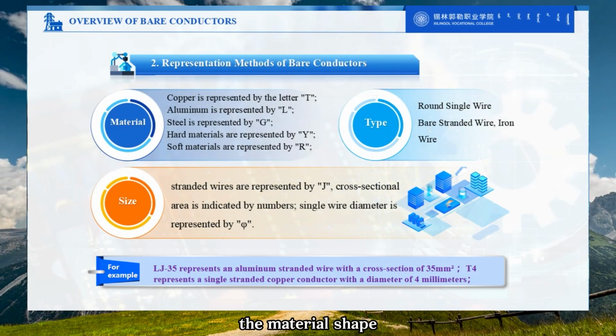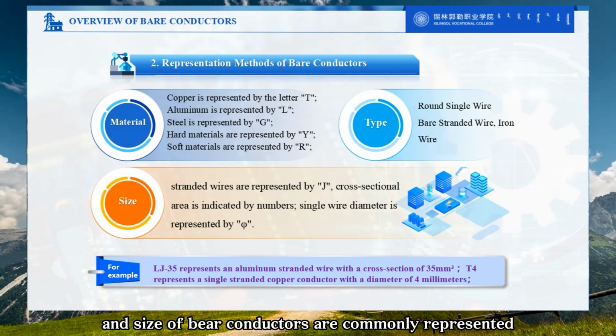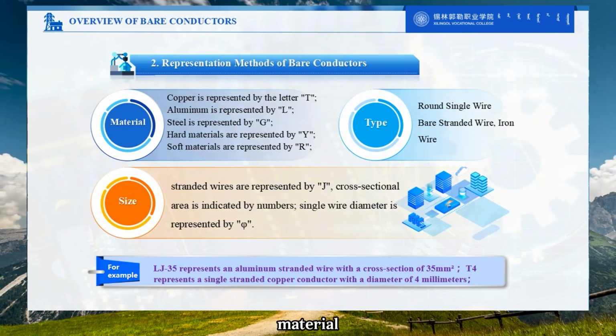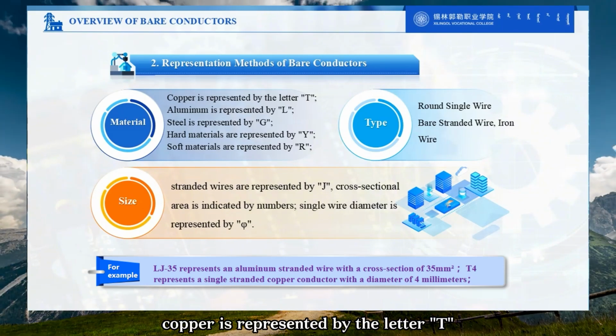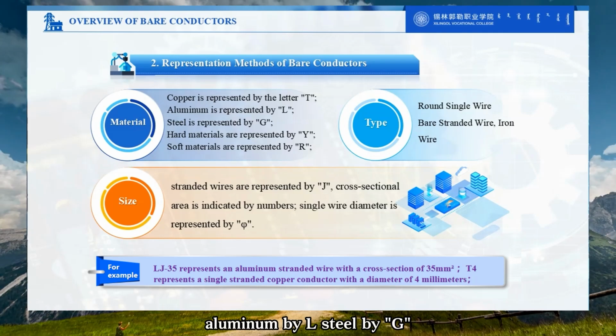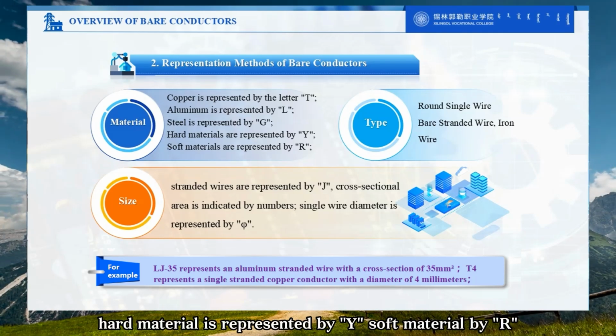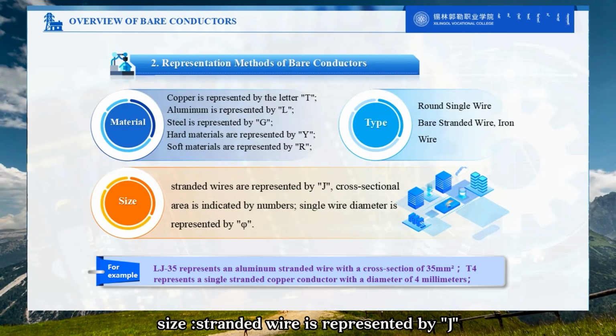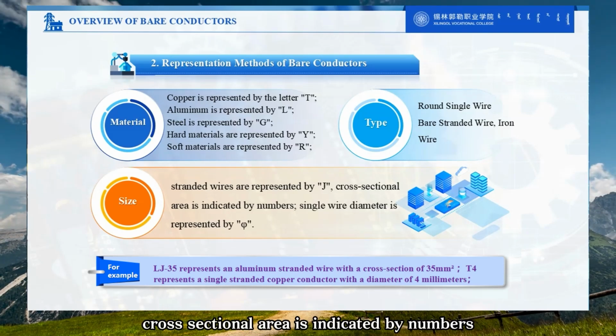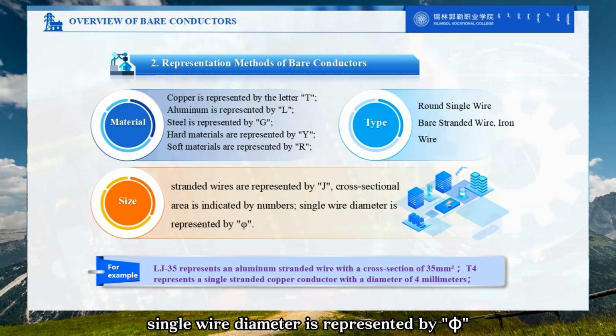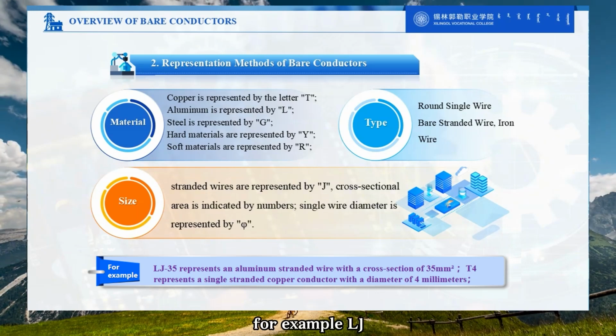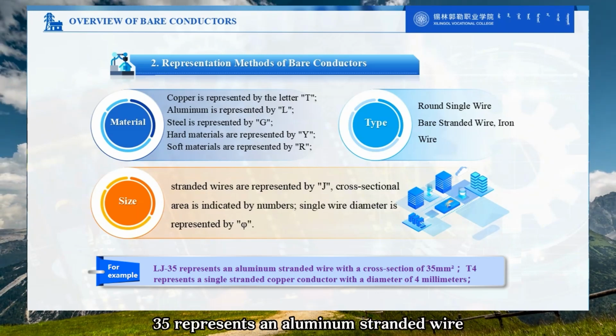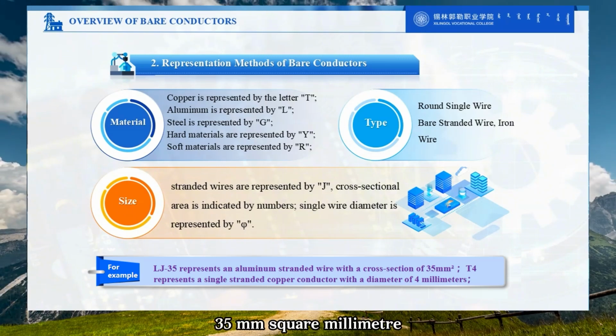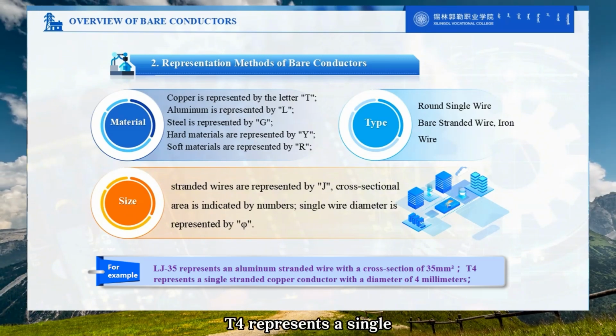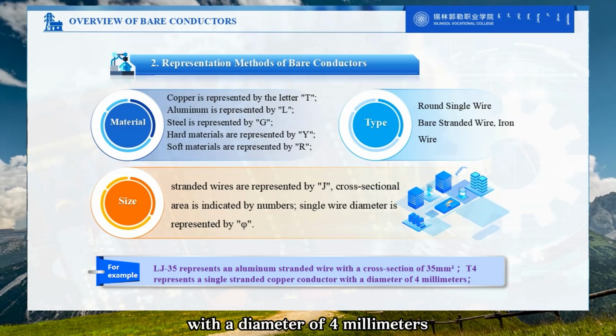The material, shape, and size of bare conductors are commonly represented by the following method. Material: copper is represented by the letter T, aluminum by L, steel by G. Hard material is represented by Y, soft material by R. Size: stranded wire is represented by J, cross-sectional area is indicated by numbers. Single wire diameter is represented by phi. For example, LJ-35 represents an aluminum stranded wire with a cross-section of 35 square millimeters. T4 represents a single-strand copper conductor with a diameter of 4 millimeters.